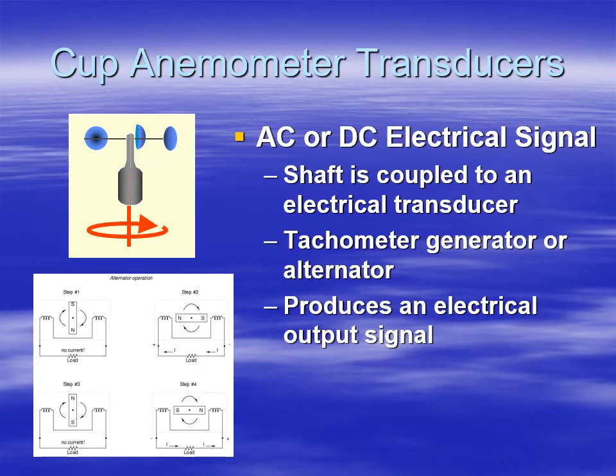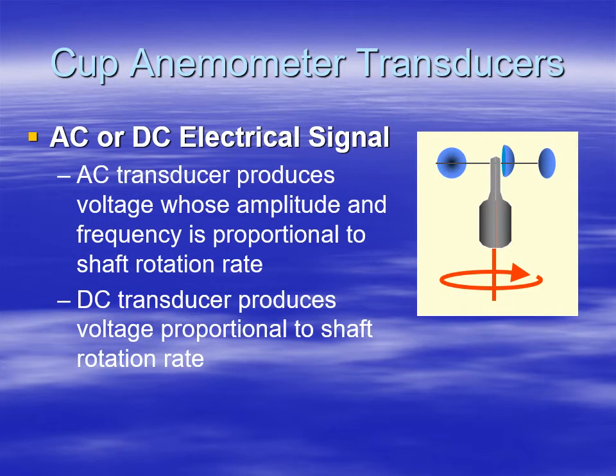We can measure the current. It could be done either AC or DC. DC would strictly be magnets. AC would be an electromagnet that's generated using an alternator, similar to an alternator. So I think you're familiar with generators and alternators, and this is more or less the electric signal that's generated. So of course, the faster the cup wheel rotates, the greater the current. If it's an AC transducer, then the voltage that's produced, its amplitude and its frequency, will be proportional, of course, to the shaft rotation. But if it's strictly DC, then the voltage is proportional to the rotation rate.